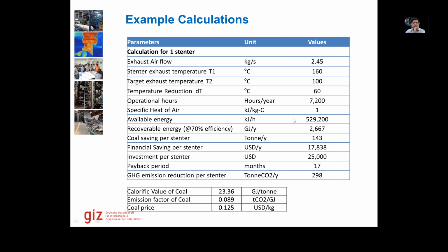So it's simply using Q equals mCp delta T, and then using the efficiency values to come to a realistic amount of recoverable energy in the heat exchanger, and also using efficiency values of the oil heater to come to a coal value. That is how we calculate the financial savings. As you can see, the payback period is 17 months. We could also calculate IRR in this case, which would also be very, very high.